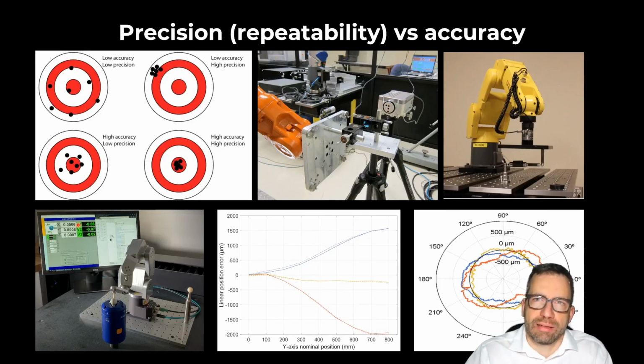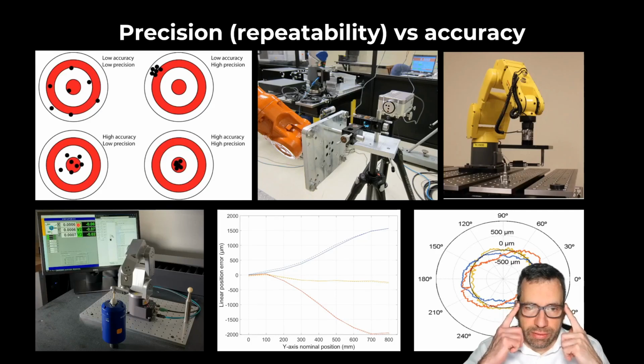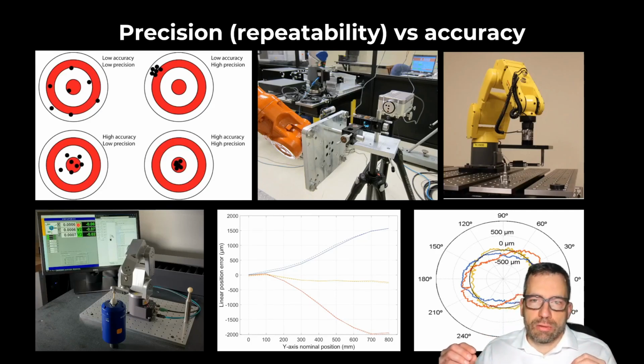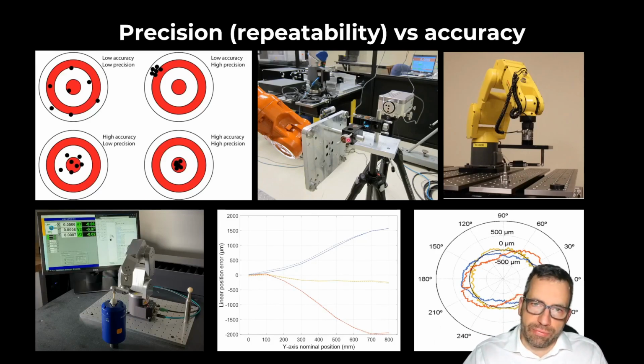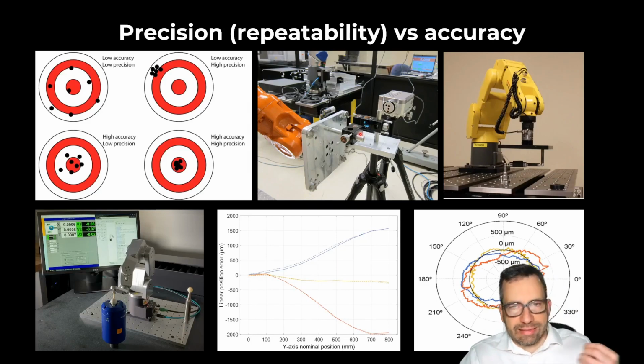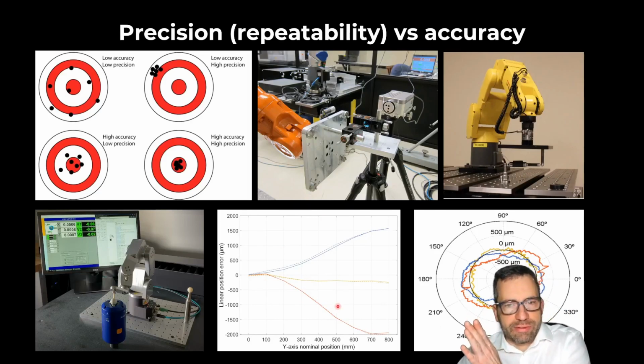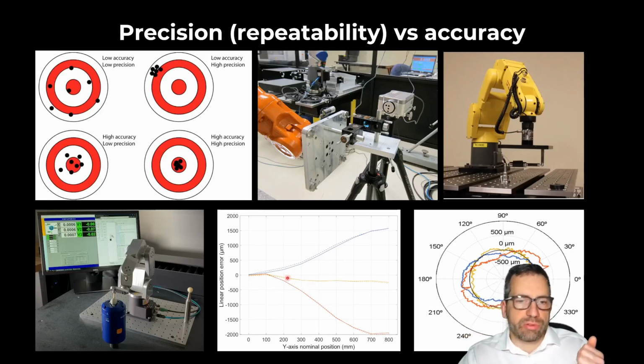So this is repeatability. I mean, repeatability is a bit more complicated. There is a formula and so on, but basically this is repeatability. Now, accuracy is completely different. In this case, it's a relative accuracy. You use a laser interferometer, which is basically a tool for measuring very, very precisely motion along a line. So in this case, we just measure the linear displacement along a line, from 0 to 800 millimeters displacement, on 3 different robots.